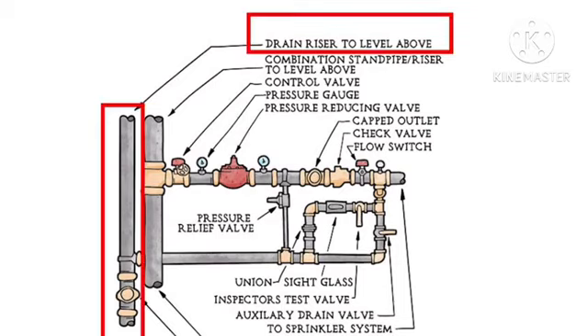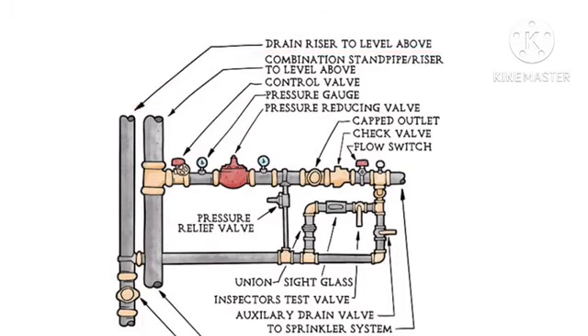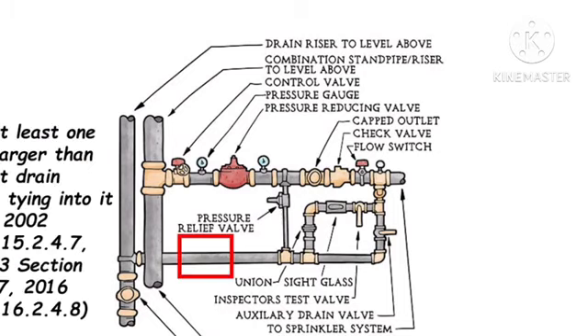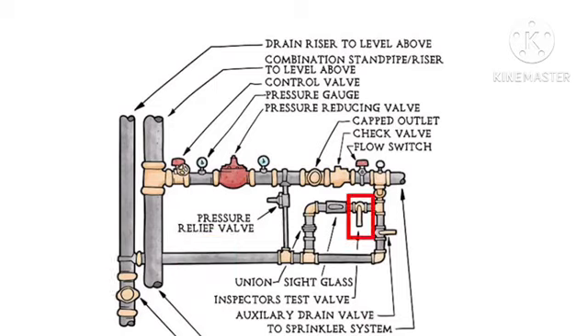Drain riser. Discharge must be to outside or to a drain capable of handling the flow. Size must be at least 1 pipe size larger than the largest drain connection tying into it. Inspector's test. Must be accessible and must discharge outside or to a drain capable of handling the flow. Must be downstream of the water flow alarm. Pressure gauge. Required at each floor control valve.